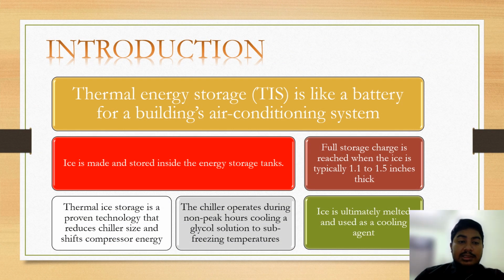So for the introduction, thermal energy storage, TIS, is like a battery for a building air conditioning system. Ice is made and stored inside the energy storage tanks. Full storage charge is reached when the ice is typically 1.1 to 1.5 inch thick. Thermal ice storage is a proven technology that reduces chiller size and shifts compressor energy. The chiller operates during non-peak hours, cooling a glycol solution to sub-freezing temperature. Ice is ultimately melted and used as a cooling agent.